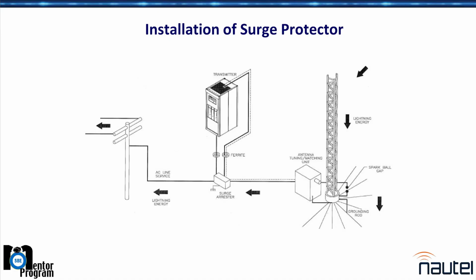So the surge protector is a bidirectional path—whether it's a big surge coming down the tower that we're dissipating onto the millions of miles of wire the power company provides, or a surge because we're at the end of the line and Farmer John fired up the irrigation machine, now we're getting a bunch of crap coming in on the AC lines. Either way, the surge protector will conduct it from tower to power line or from power line to ground. But it needs to be installed.